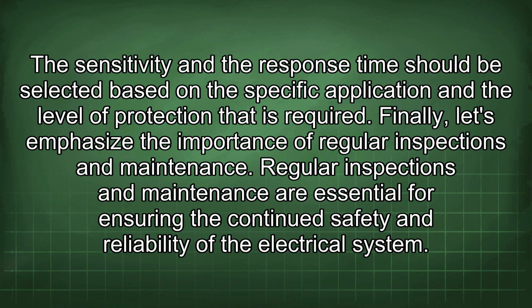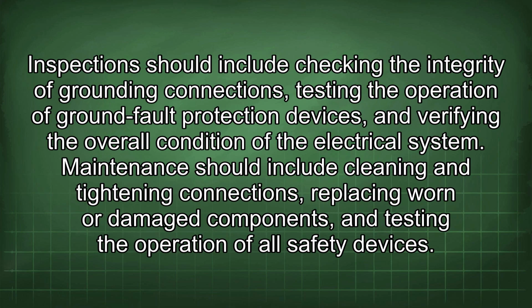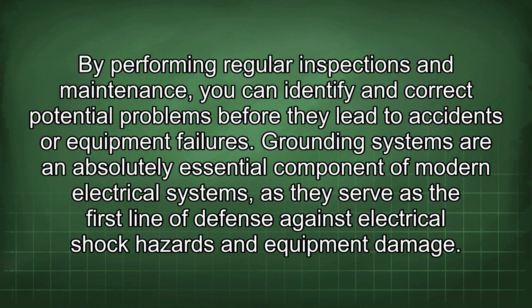Finally, let's emphasize the importance of regular inspections and maintenance. Regular inspections and maintenance are essential for ensuring the continued safety and reliability of the electrical system. Inspections should include checking the integrity of grounding connections, testing the operation of ground fault protection devices, and verifying the overall condition of the electrical system. Maintenance should include cleaning and tightening connections, replacing worn or damaged components, and testing the operation of all safety devices. By performing regular inspections and maintenance, you can identify and correct potential problems before they lead to accidents or equipment failures.